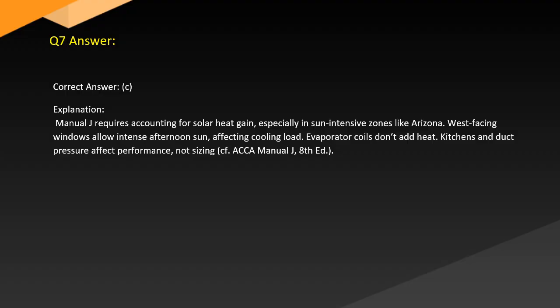Answer. Correct answer: C. Explanation. Manual J requires accounting for solar heat gain, especially in sun-intensive zones like Arizona. West-facing windows allow intense afternoon sun, affecting cooling load. Evaporator coils don't add heat. Kitchens and duct pressure affect performance, not sizing. Cf. ACCA Manual J, 8th ed.